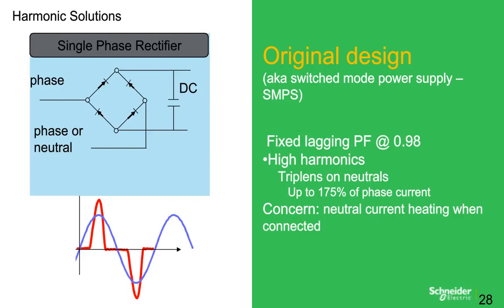The switch mode power supplies connected phase to neutral cause very large levels of triplen harmonics. And again, for purposes of definition, triplen is basically the odd multiples of the third harmonic. So for example, the 3rd, 9th, 15th, and 21st, which can lead to very high current circulating on the neutral, and unless the neutral is sufficiently oversized, this could present a pretty significant fire hazard, or just in general, oversizing your equipment.